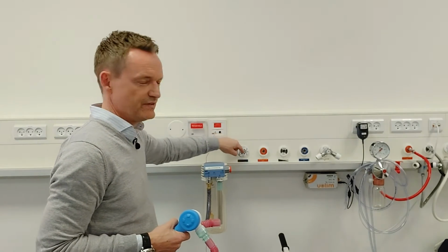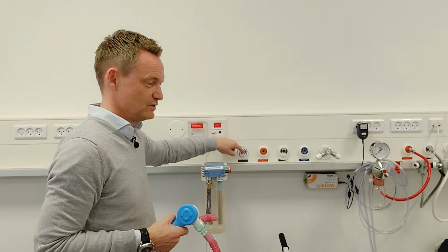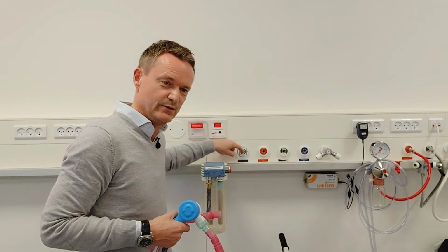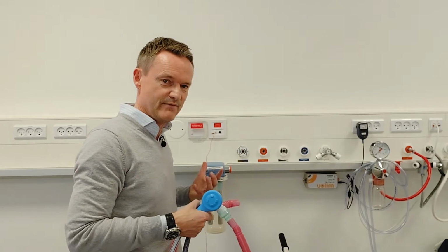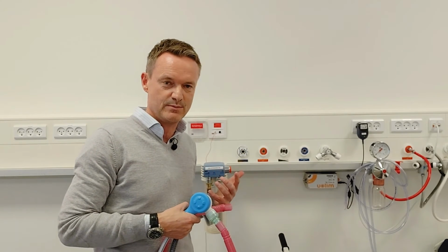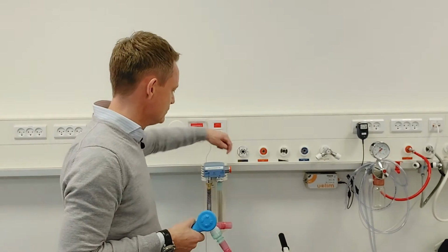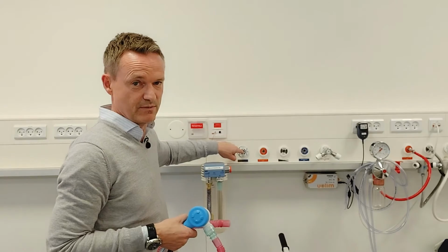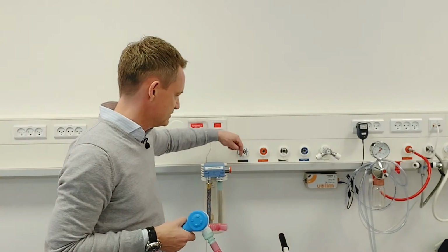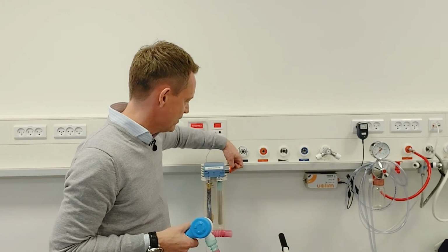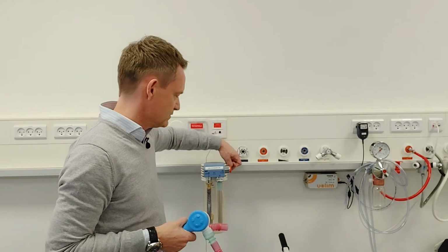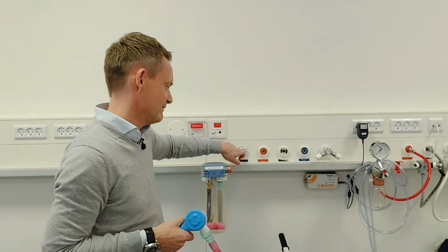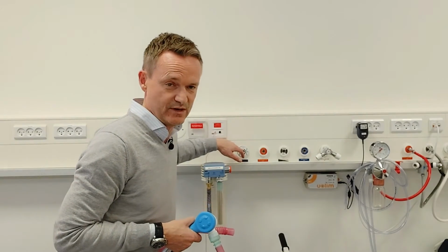If something happens on the AGSS side and all of a sudden you have a very high vacuum, you don't want that high vacuum to influence the patient. They don't need that high vacuum to generate any possible damage to their lungs. That's why you have the holes on the side, meaning that if all of a sudden it turns up very high, that high vacuum will simply be placed on the holes here on the side. So that's the buffer from a high negative pressure generated from a vacuum pump that possibly goes up very high.